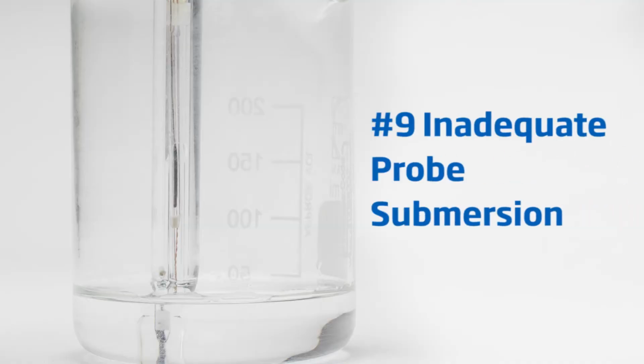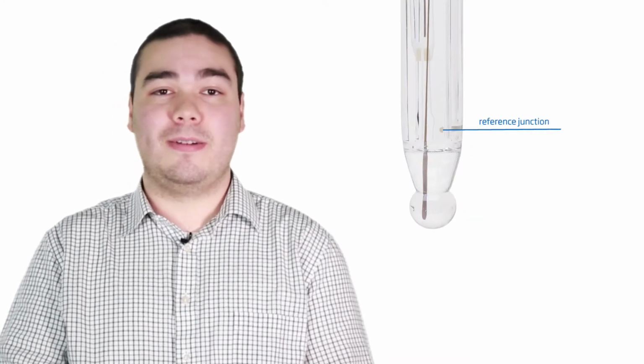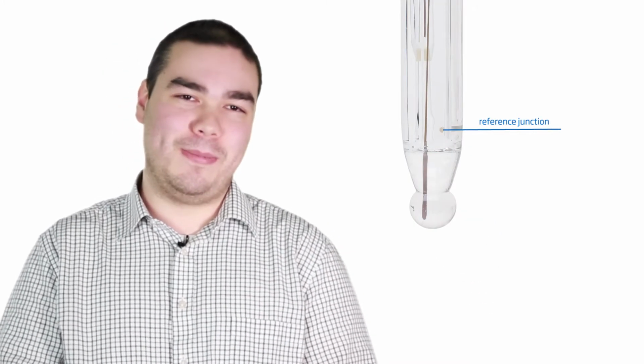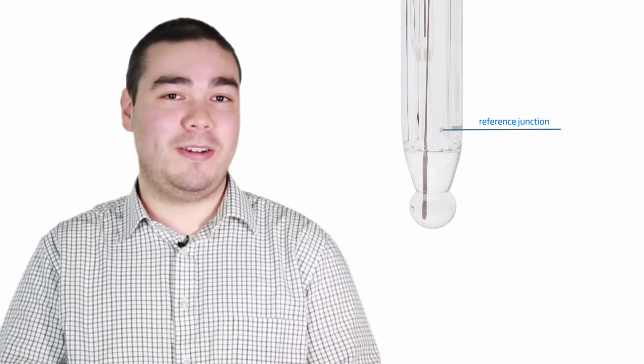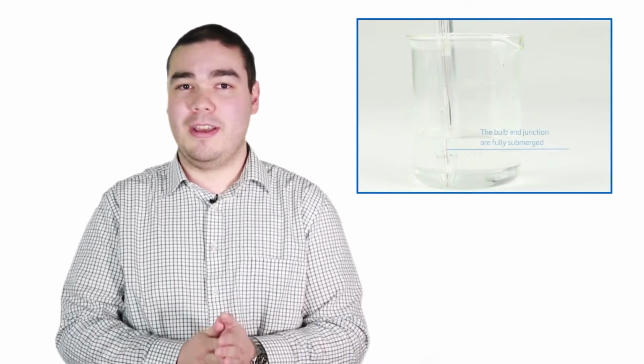Number 9, inadequate probe submersion. pH electrodes are built with a junction near the bottom of the glass. When measuring a sample, that junction needs to be covered by the sample, along with the electrode bulb. If the junction is left uncovered, you will not only be measuring your sample, but measuring the air around it too. All you need to do is make sure you have enough solution to cover the junction to give you the most accurate readings.